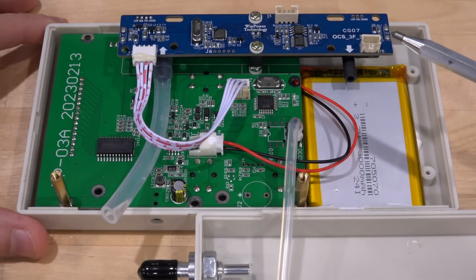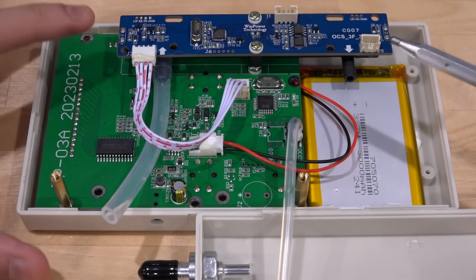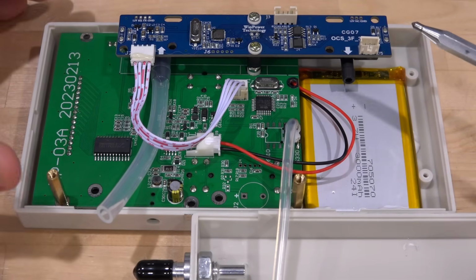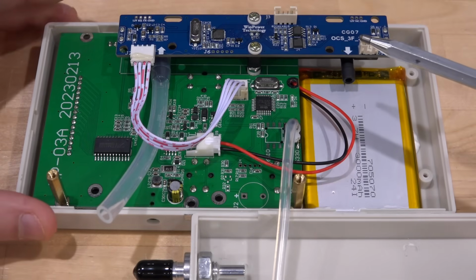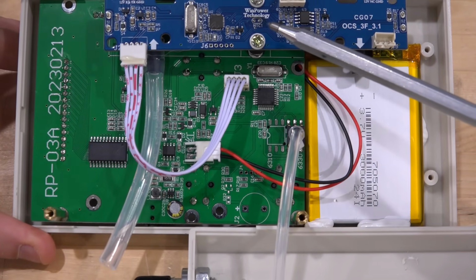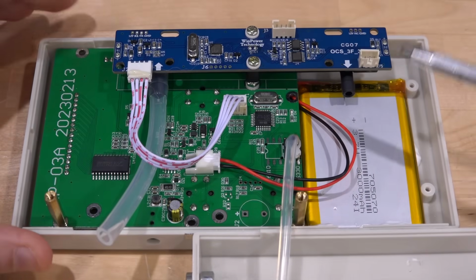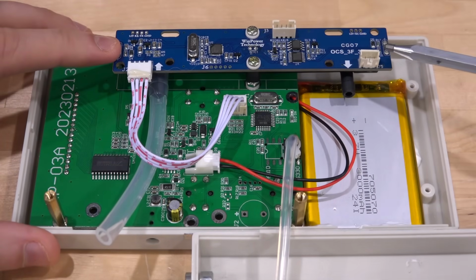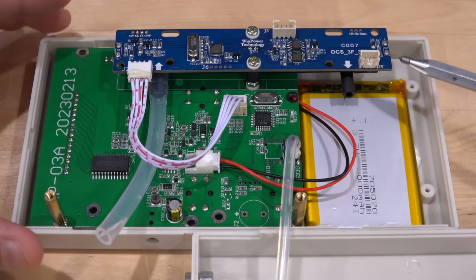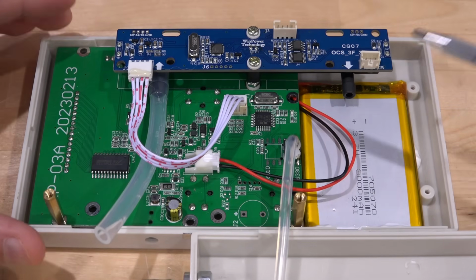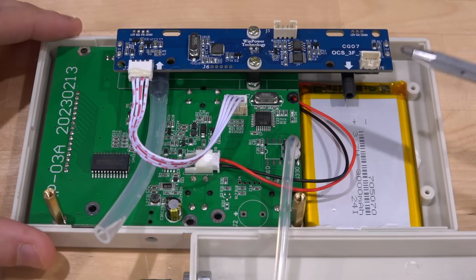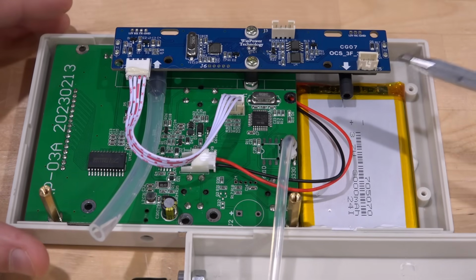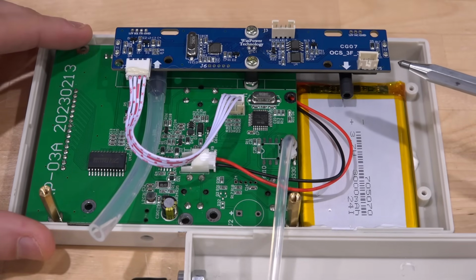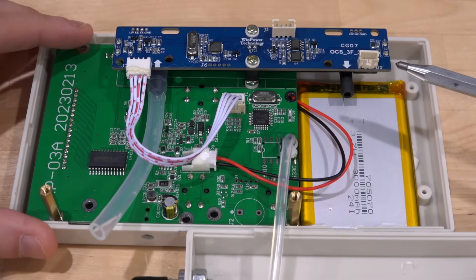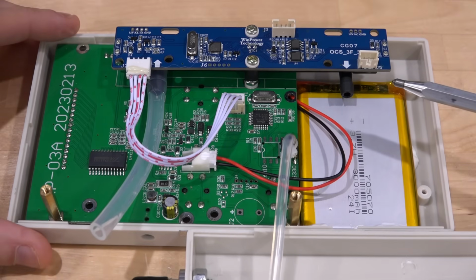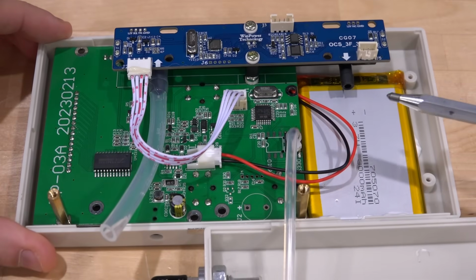Now of course, the flow can also be measured, because by measuring a Doppler shift between the two ultrasonic sensors, you can also measure the flow. If you know the temperature of the gas, and that's exactly what this little sensor down the middle is, it's just an NTC thermometer in the middle. So you measure the temperature, you look at the Doppler effect, you look at the delays, and then from that, you can estimate the density of the gas. And from that, you can estimate the relative concentration of oxygen with respect to the other gases. It's not going to be super accurate, I think plus or minus 5% or so, maybe plus or minus 3% with some good calibration, but it will work just fine in this situation. So yeah, another very clever sensor design.